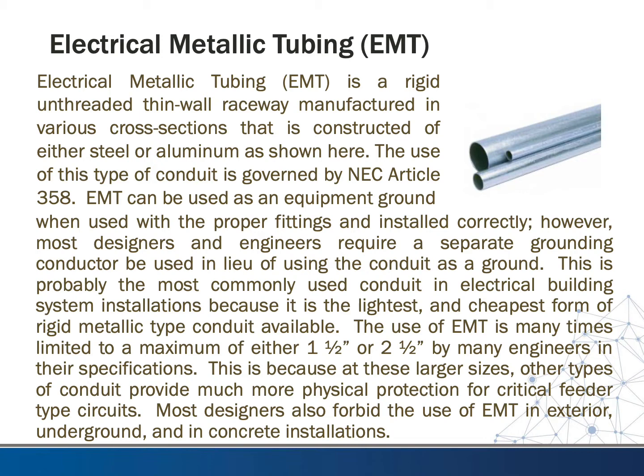Electrical metallic tubing, or EMT, is a rigid, unthreaded, thin-wall raceway manufactured in various cross sections, constructed of either steel or aluminum. Its use is governed by NEC Article 358. EMT can be used as an equipment ground with proper fittings and correct installation; however, most designers and engineers require a separate grounding conductor instead. This is probably the most commonly used conduit in electrical building system installations because it is the lightest and cheapest form of rigid metallic conduit available. Its use is often limited to a maximum of one-and-a-half or two-and-a-half inch by many engineers, since larger sizes of other conduit types provide much more physical protection for critical feeder circuits. Most designers also forbid the use of EMT in exterior, underground, and in-concrete installations.